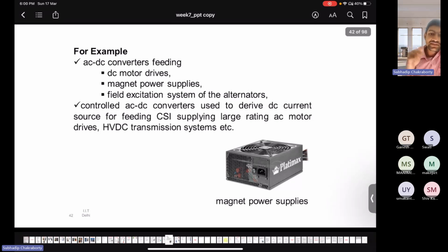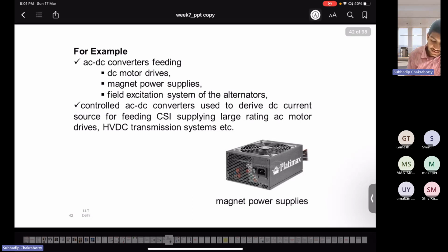From your end, you can compensate for whatever non-linearities appear due to your connected loads. The best possible thing you can do is control such that the point of the supply that is coming to your system is getting linear currents, and you can maintain unity power factor at that point. You understand what I mean? At the load PCC.